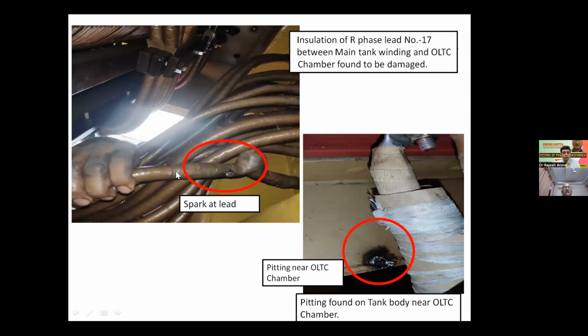See, this is lead number 17 from the R phase winding. You can see here there was some kind of a spark, and its insulation was damaged. Also, at the place where it was resting, we saw some pitting. But when the transformer was in de-energized condition, there were no vibrations. These were not exactly touching at that time, and on all our electrical tests, everything passed because there was no direct connection. However, when the transformer was energized, maybe due to the vibrations in the transformer, it was touching here and the transformer tripped. Thereafter, this insulation was repaired and this pitting was also repaired, and the transformer was energized again.